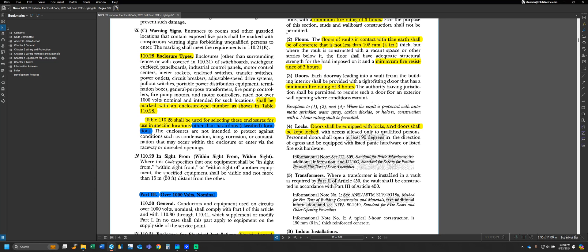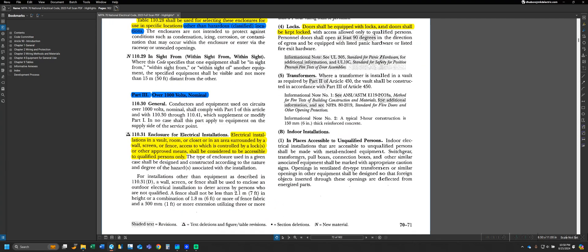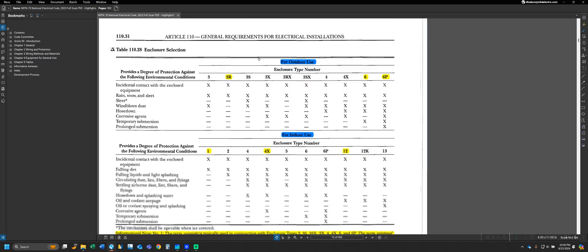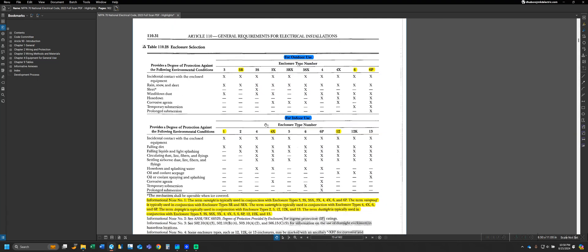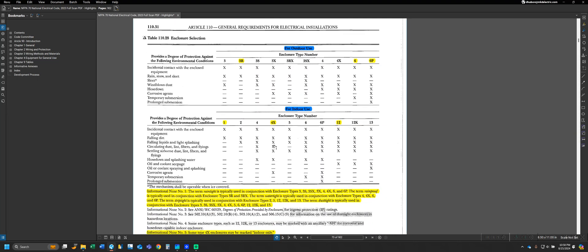We're going to go ahead and take a look at Table 110.28 and discuss it because it's a very important table to understand. If we move down slightly or to our next page, we can see that we have Table 110.28 here for enclosure selection. Anytime that we're looking to pick what type of enclosure we want to use to protect electrical equipment or to install electrical equipment in, then this would be our reference for that. The way Table 110.28 works is we can see we have one half of the table for outdoor use and one table for indoor use. As we previously mentioned with tables and understanding our columns and rows, we see our first column is provide a degree of protection against the following conditions. In other words, will the enclosure protect against this item?